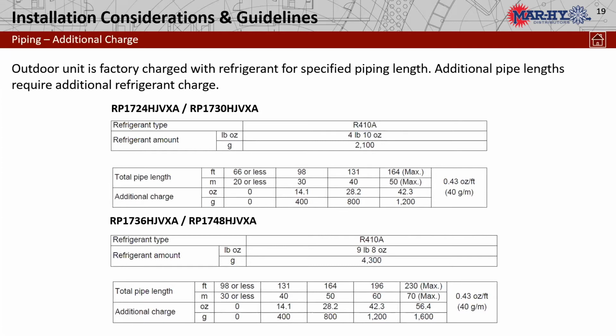Now, the 2-ton and 2.5-ton outdoor unit has 4 pounds, 10 ounces of refrigerant. On the 2-ton and 2.5-ton, we can go 66 feet without having to add any refrigerant. We are good to 66 feet. You don't have to pull any out. You don't have to put any in. And we can go up to 164 feet. Now, anything over 66 feet, we would need to add 0.43 ounces per foot for added refrigerant. That's on the 2 and the 2.5-ton.